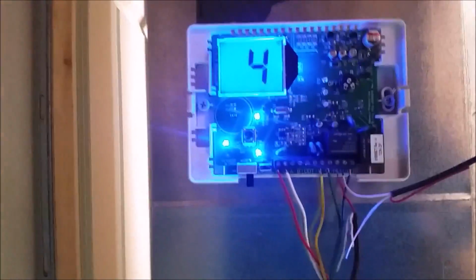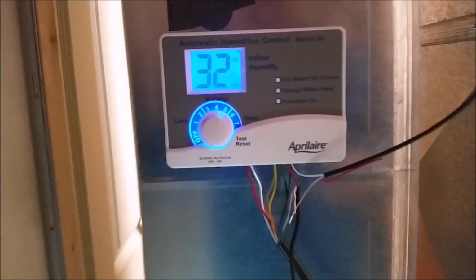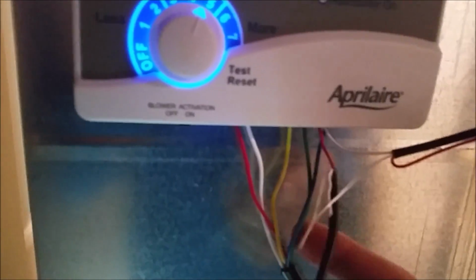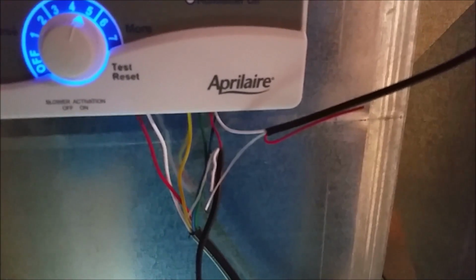Notice I just got my power back here, which is great. When you're working on all this stuff, don't rely on that little switch in your furnace to turn off all the power. Make sure you turn off the power at your circuit panel to reduce any risk of getting shocked. One thing I'll mention, when you're using all this wire for your low voltage and everything, the EAC port and the neutral, make sure you don't use your low voltage wire there.